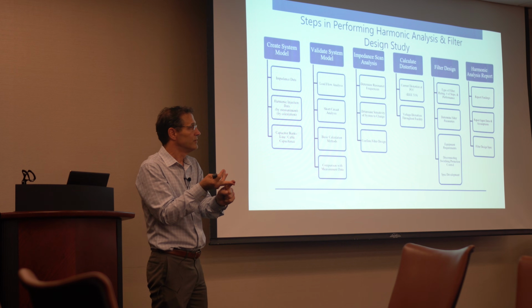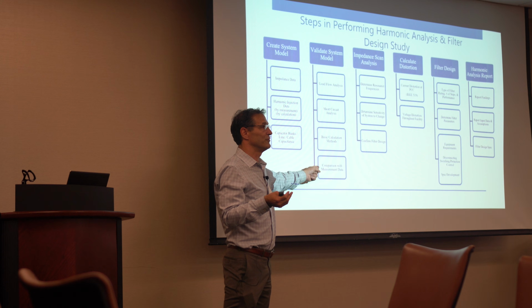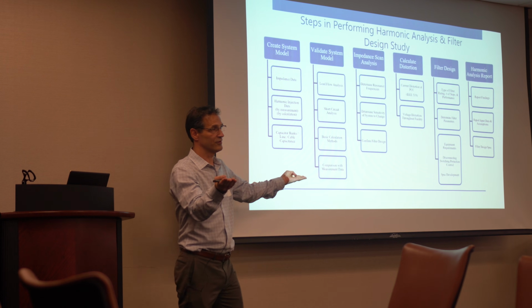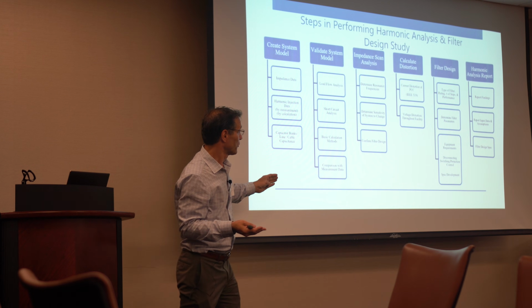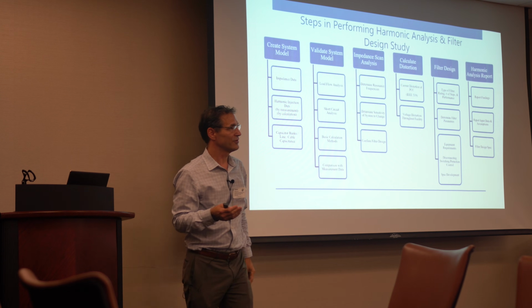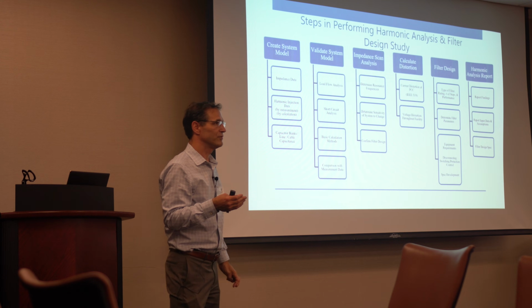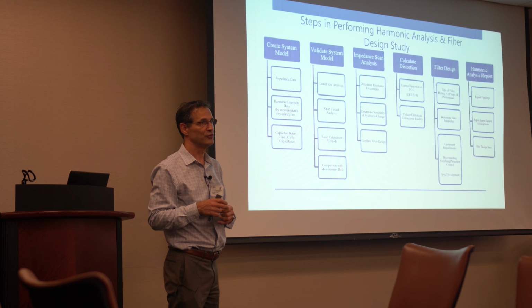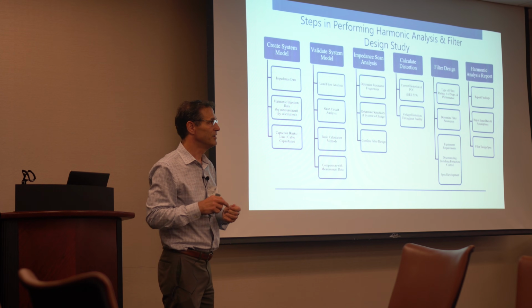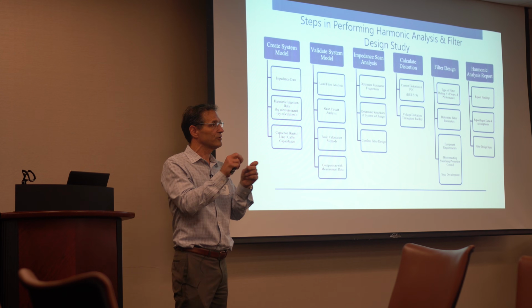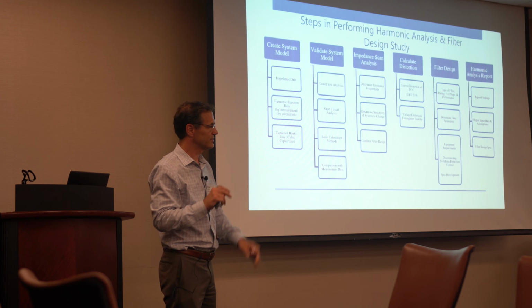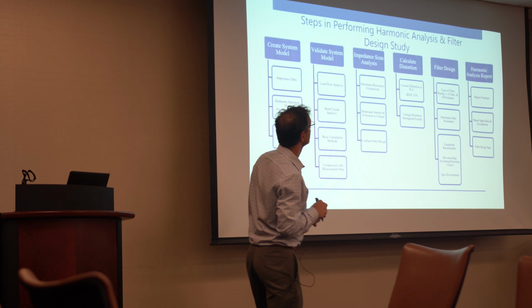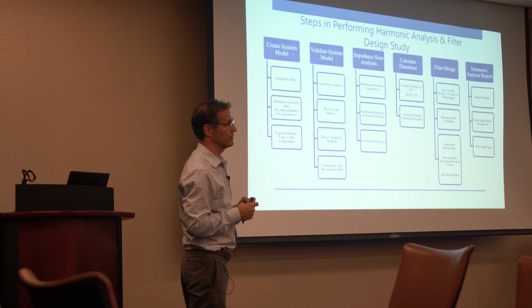They do that, okay, then you compare it to your study. You compare the study to the real world. It's very difficult to get those to match up. So I tend to try to stay away from doing that. You've taken a study that might take a week and changed it to two or three weeks, because you think something is wrong. I'm going to start fooling around with impedances, and it's very difficult. So I say don't do it. And it doesn't matter in the end, really.